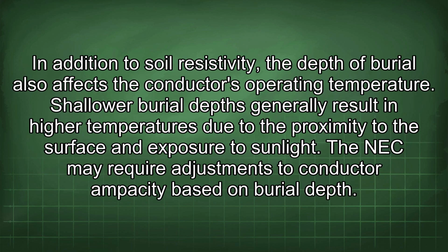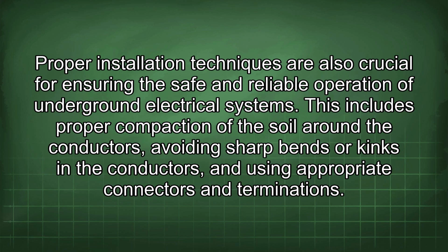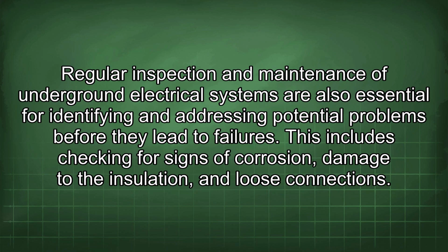In addition to soil resistivity, the depth of burial also affects the conductor's operating temperature. Shallow burial depths generally result in higher temperatures due to the proximity to the surface and exposure to sunlight. The NEC may require adjustments to conductor ampacity based on burial depth. Proper installation techniques are also crucial for ensuring the safe and reliable operation of underground electrical systems. This includes proper compaction of the soil around the conductors, avoiding sharp bends or kinks in the conductors, and using appropriate connectors and terminations. Regular inspection and maintenance of underground electrical systems are also essential for identifying and addressing potential problems before they lead to failures.